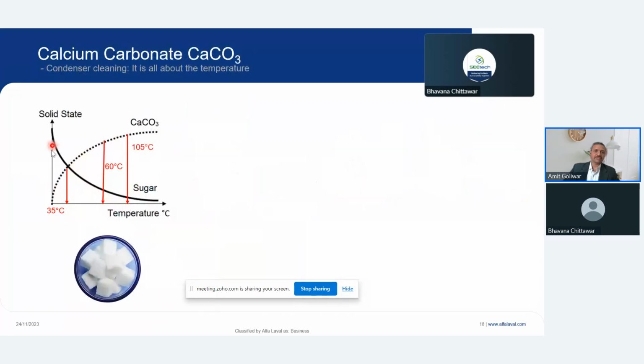How it is so relevant, for that we need to understand how calcium carbonate behaves. This is a typical example: calcium carbonate doesn't work like sugar. When you increase temperature, the solubility of sugar increases, but in calcium carbonate, the solubility reduces. So if you look at your water geyser or tea making machines, you will find that scale formation is very high on the coil. And why is it high? Because calcium carbonate sticks on the hot surface faster.